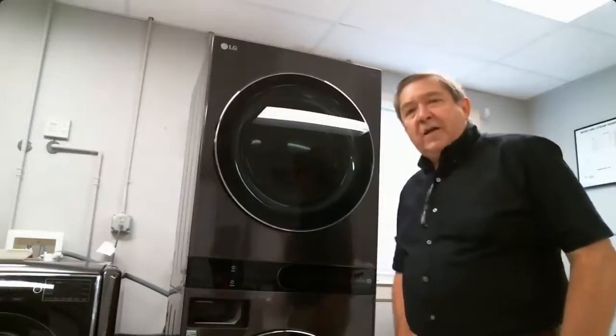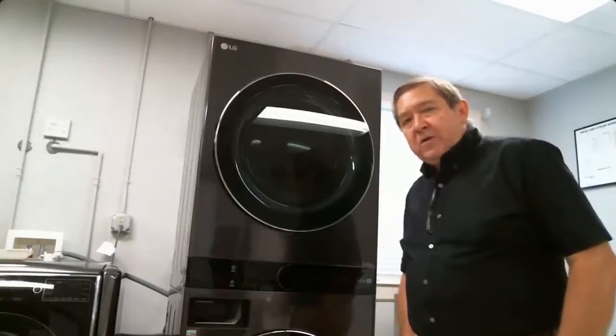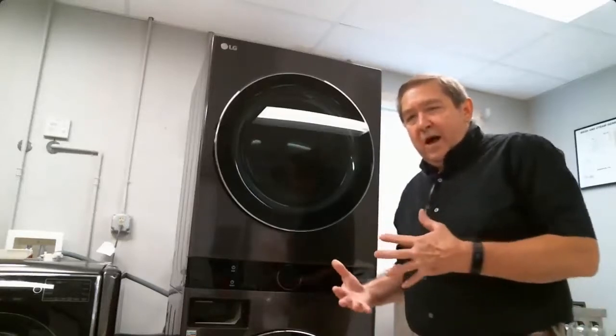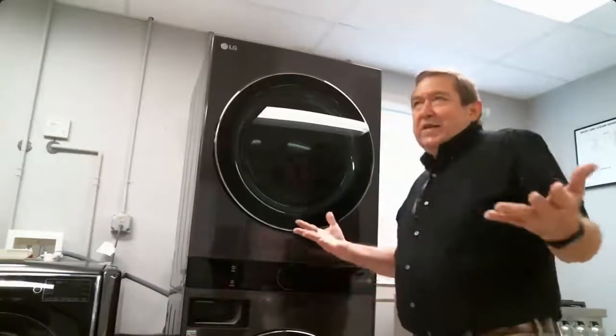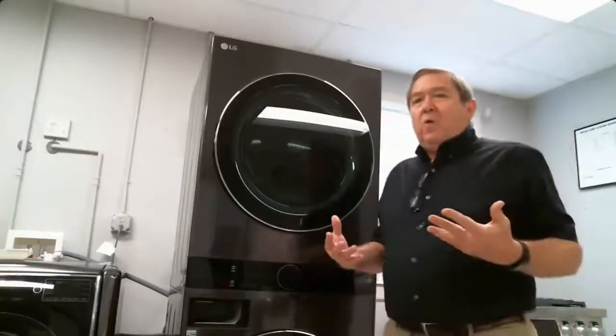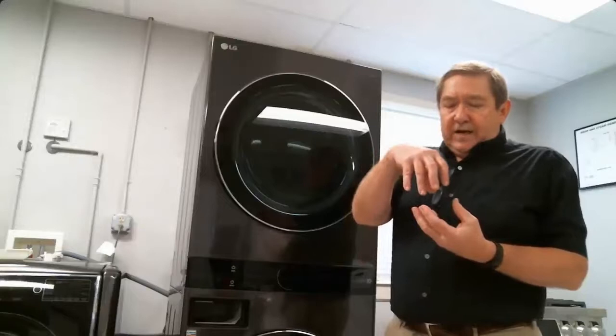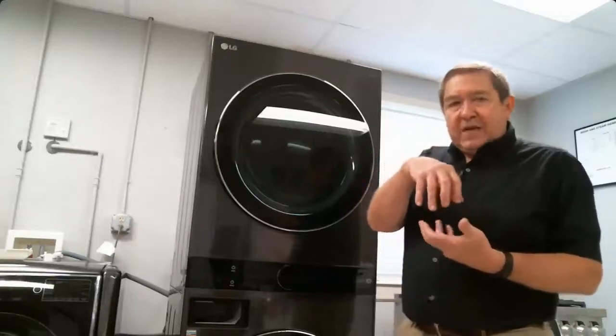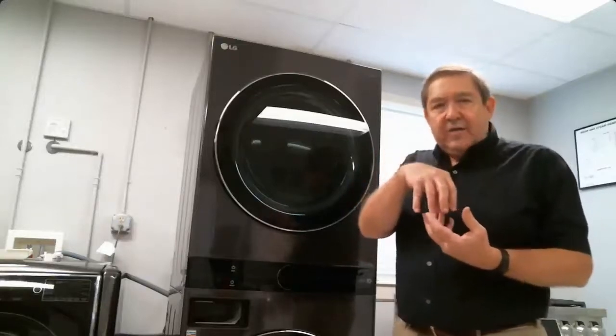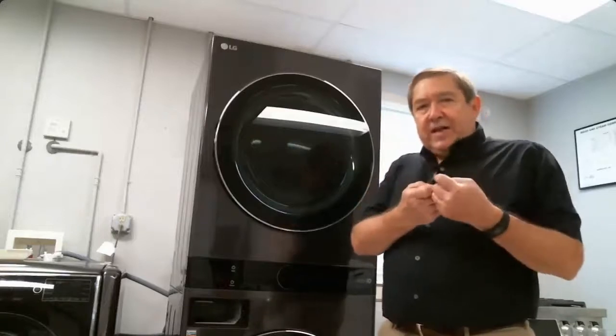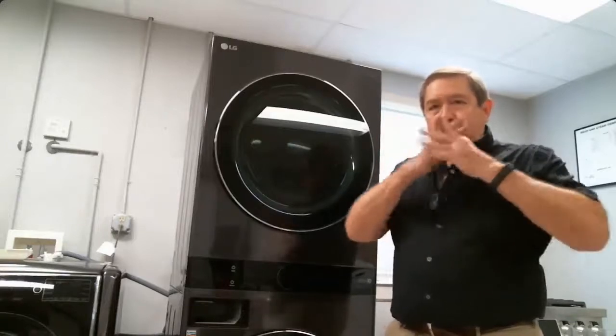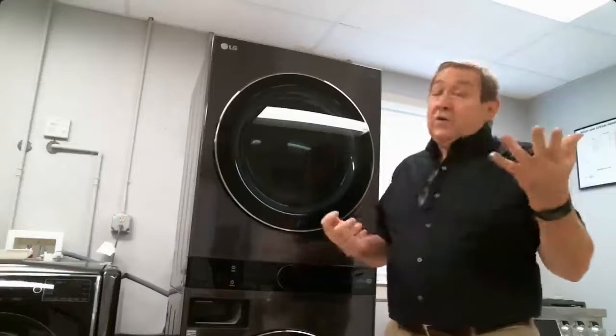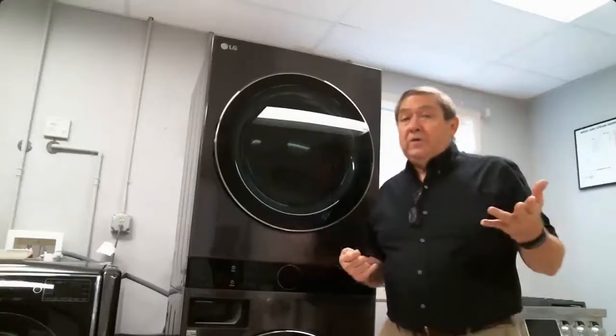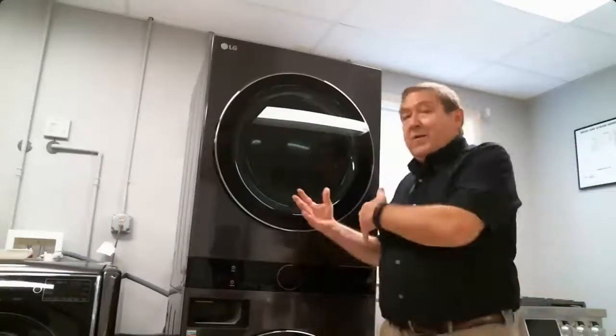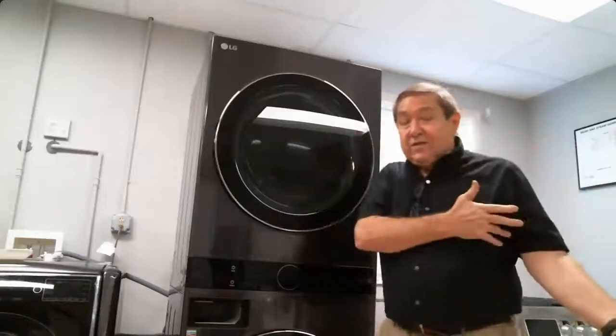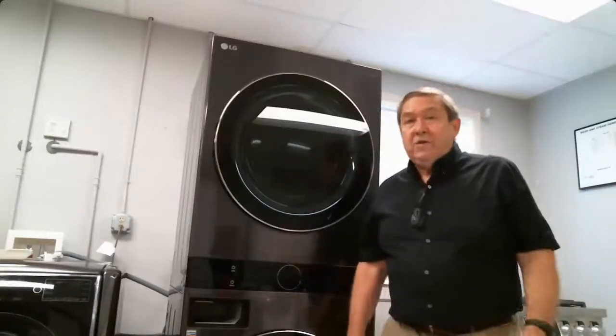Well, don't forget we had different gauge wires when talking about one to the other - I shouldn't say different gauge, they were actually the same. But we had a problem when we took those connectors and put them in a plastic bag. Sometimes what you get is condensation inside there. The condensation stresses out those connectors, so eventually that thing is moving and eventually they do break. So you made a good point - one of the things you want to check, before you start condemning main boards and hall sensors, is make sure we don't have a loose connection.